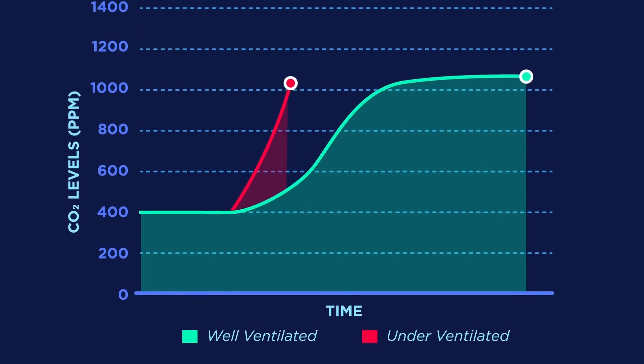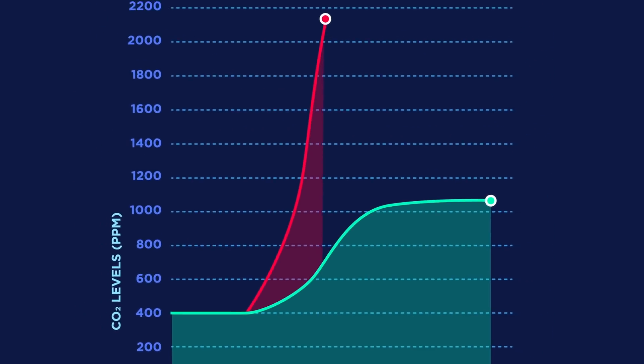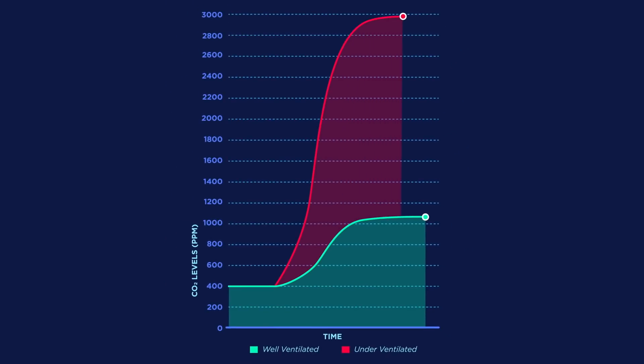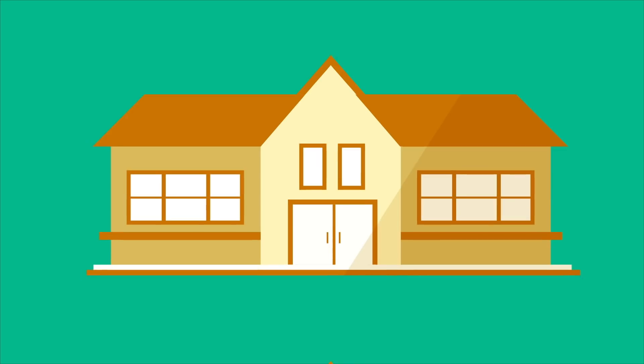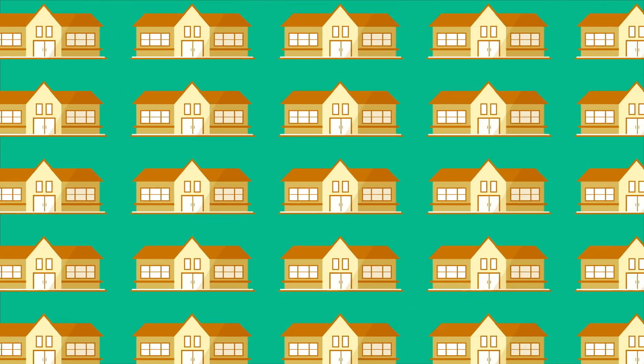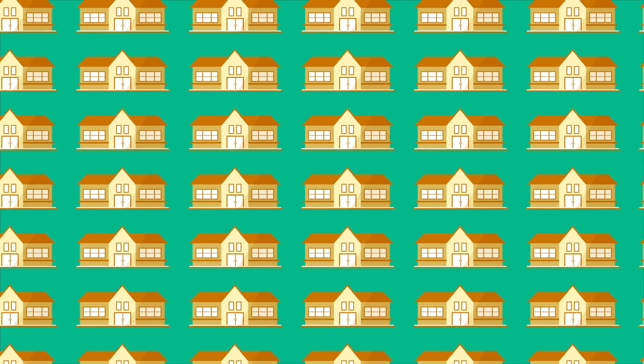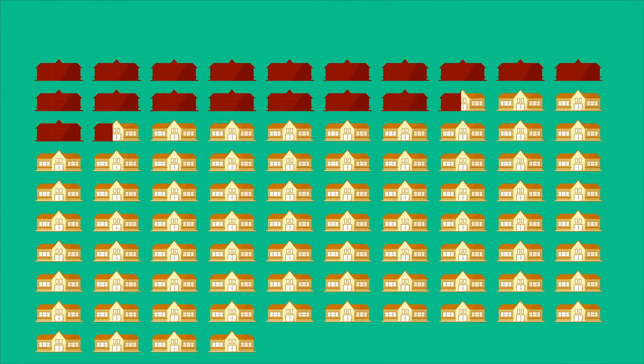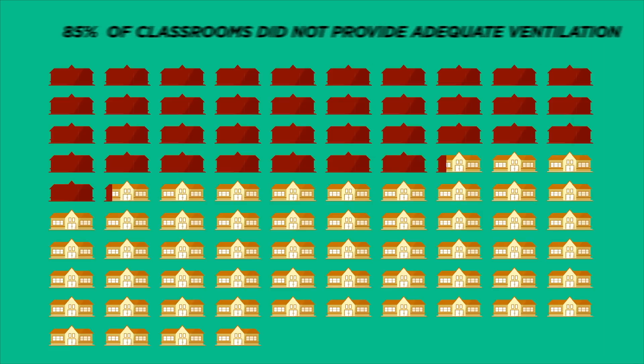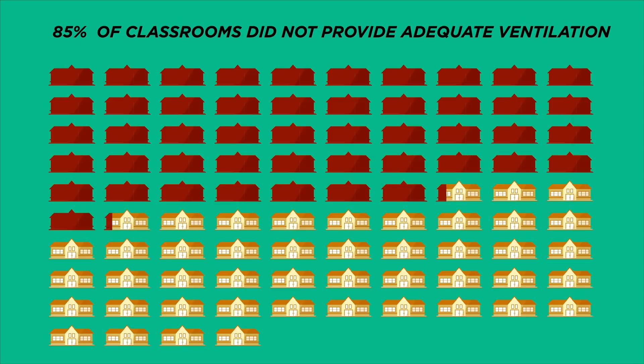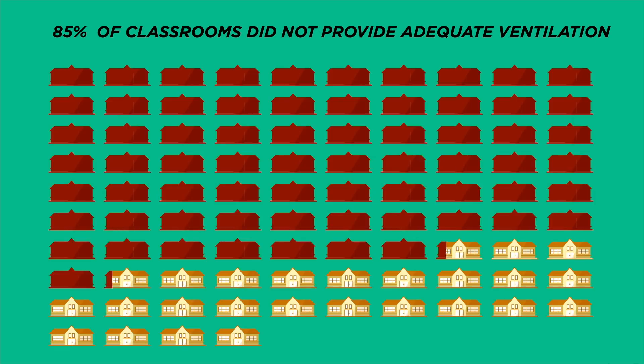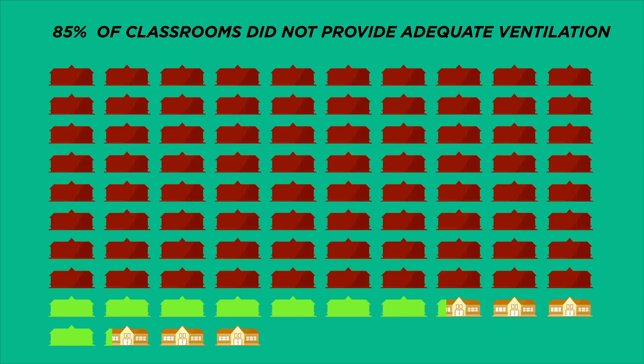In a classroom with ventilation problems, CO2 will keep climbing, sometimes as high as 3,000 ppm. Research from around the world shows there are high CO2 levels in many classrooms. For example, in a 2019 study, researchers found that about 85% of 94 recently installed HVAC systems in California K-12 classrooms did not provide adequate ventilation.